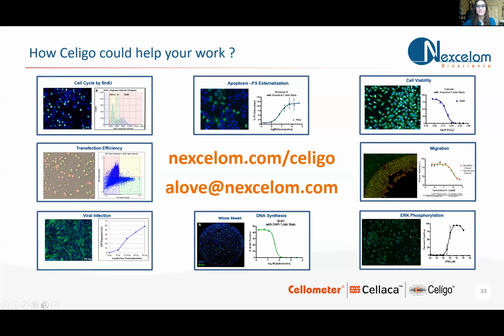Wonderful. And then from Thomas Miller, what and how many fluorescent parameters can be measured? That's a great question. So you have 5 different colors that you can work with. So you can identify things like number of objects, fluorescent intensity on a per object basis, or normalized to size of the cell. So we use both a mean intensity or fluorescent intensity. You also get parameters such as size, XY position, co-localization. So you can do a lot of the gating interfaces that you would apply with flow, where you're looking for, say, double positives or single positives or things like that as well.